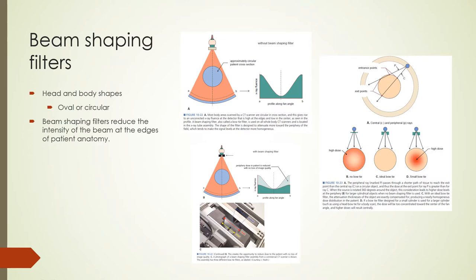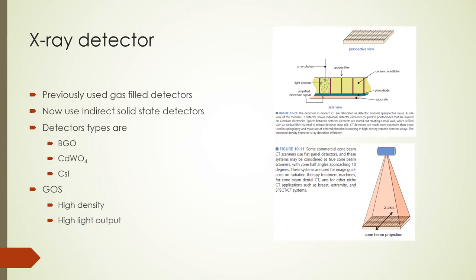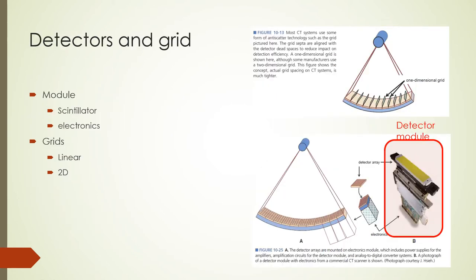In older generation CT scanners, gas-filled detectors were used. Now CT detectors use scintillation crystals for converting X-rays to visible light — made of bismuth germanate, cadmium tungstate, cesium iodide, or gadolinium oxysulfide, which has high density and high light output. Each scintillation detector module has associated electronics with gain channels and an analog-to-digital converter. There is an anti-scatter grid between each module, which can be linear or 2D.